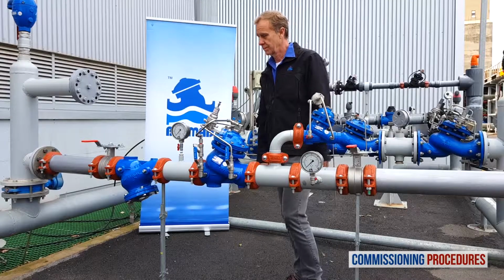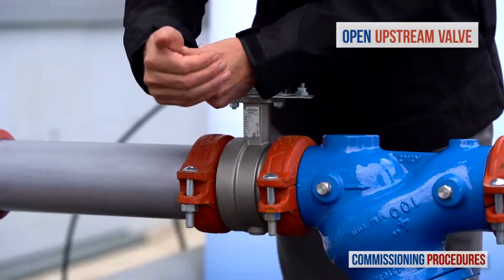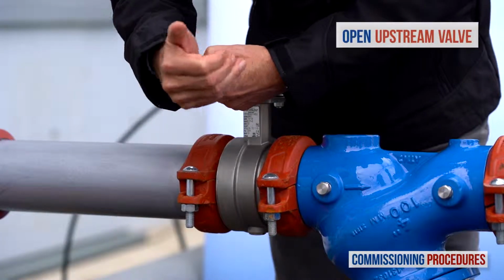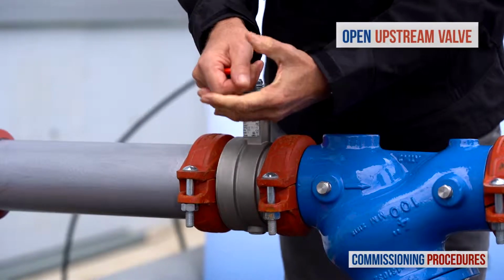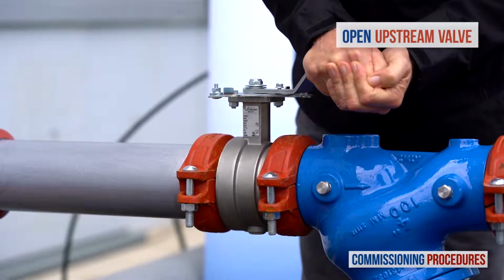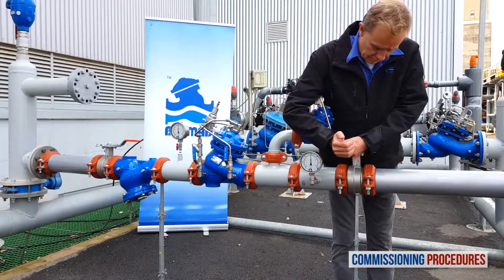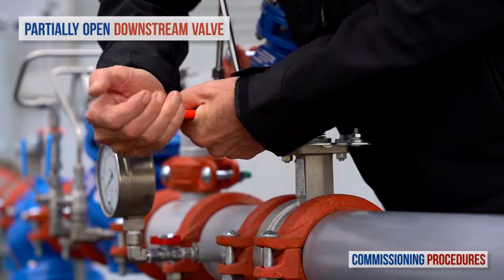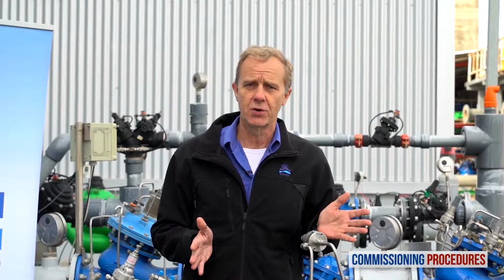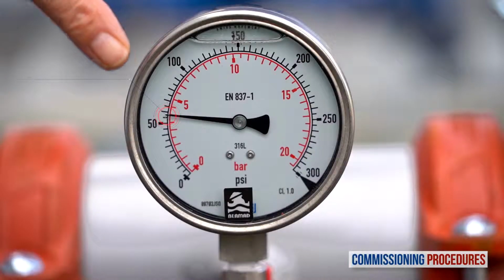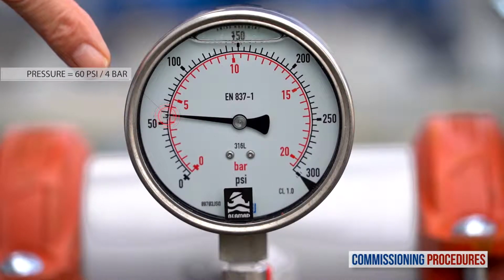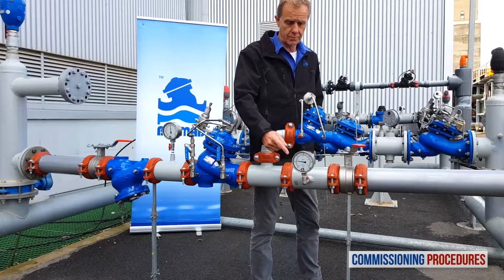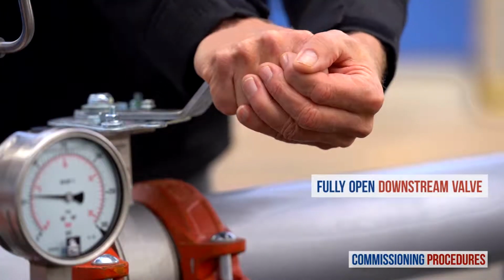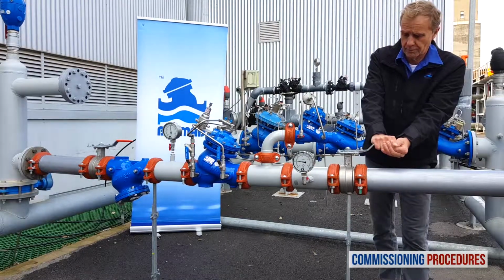Alright, now slowly fully open the upstream isolating valve to fill the station with water. Proceed by partially opening the downstream isolation valve. At this stage, if you haven't released the pilot's adjustment screw of the reducing valve, the consumer's line connected to the station will fill in a slow and controlled manner. All you need to do now is to check that the downstream pressure is compatible with your requirements. And when pressure has stabilized, continue to fully open the downstream isolation valve.